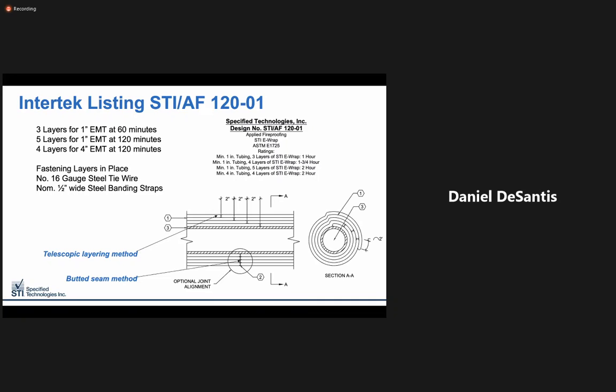Regardless of which method is used, we allow for the use of 1/2-inch banding coil or 16-gauge tie wire on the outermost layer to fasten in place. Banding coil provides a cleaner aesthetic, whereas tie wire may be a quicker installation, but both are accepted under this Intertek listing.